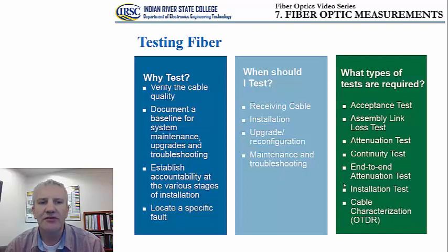Another reason why we are doing the testing is to document a baseline for the system maintenance, upgrades, and troubleshooting. So once a fiber optic link is installed, we want to record the performance of that fiber optic link so that later on, if there are any issues during the operation a few years later, we are able to have some sort of a reference as to how the fiber optic link performed when it was installed.